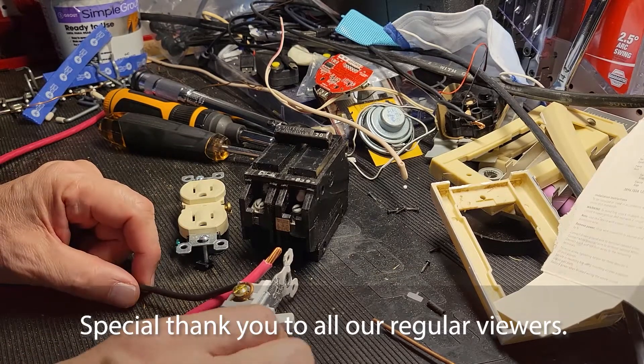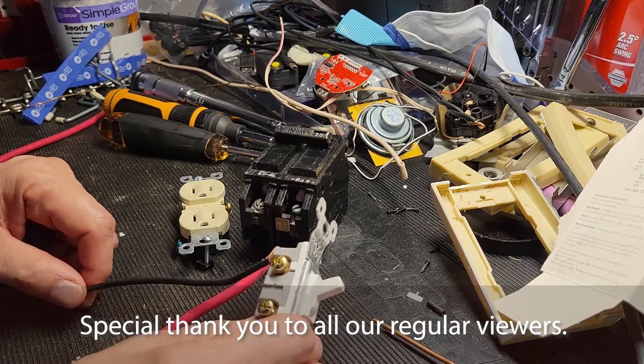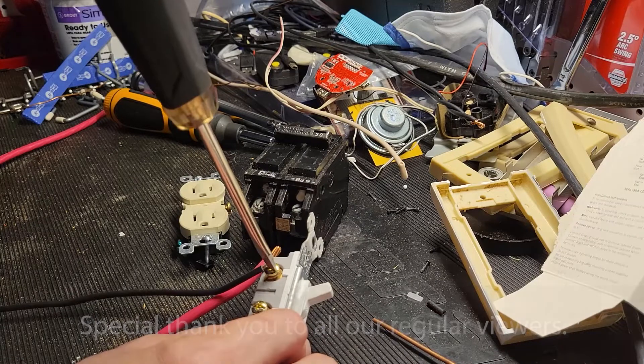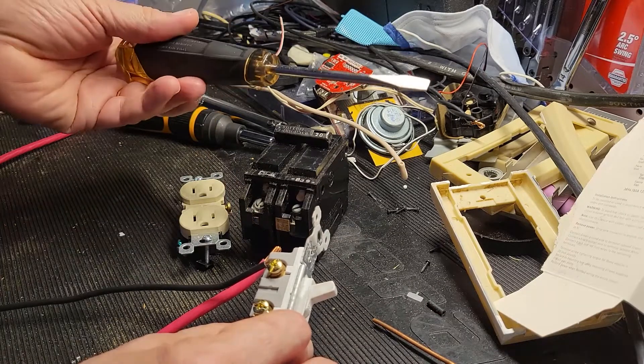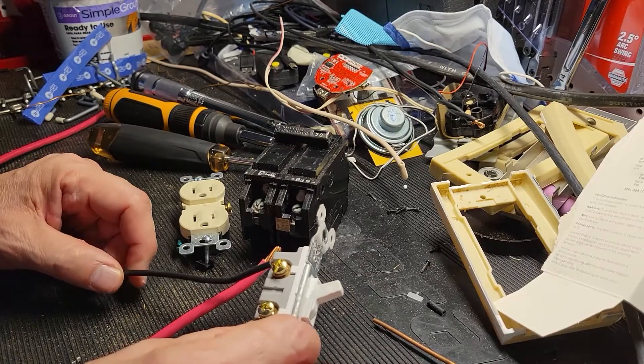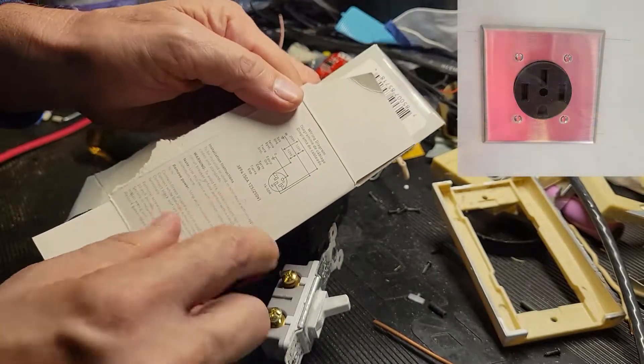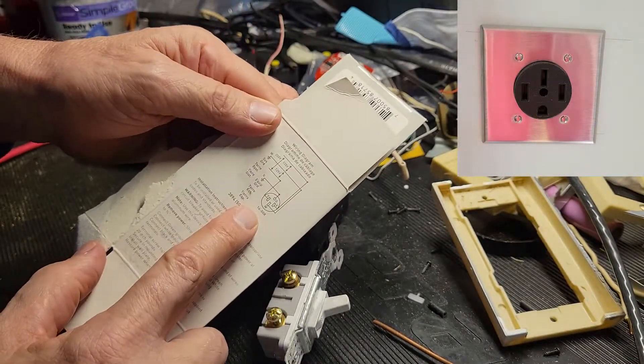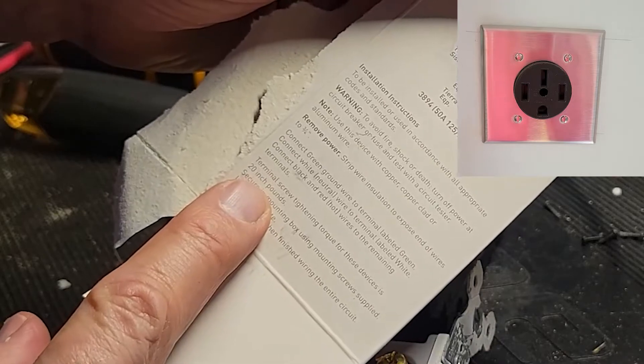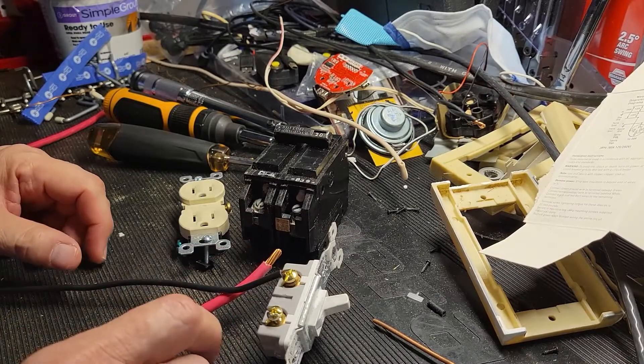Regular viewers to this channel have seen me install switches and receptacles, and usually when we go to make that connection, I'll say just turn the fastener until it's really snug. I didn't give a value — I didn't know what the value was. Turns out there are values. For example, on this product right here, which is a 14-50 receptacle, it says there's a 20 inch pound setting for torque for the fasteners on it.